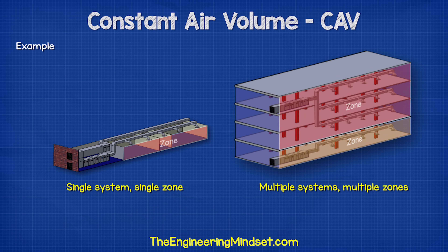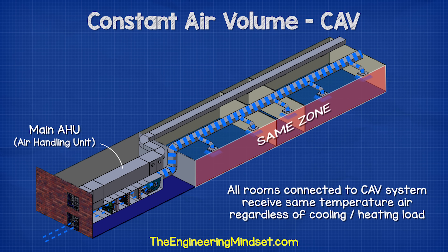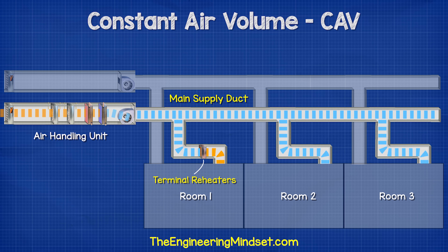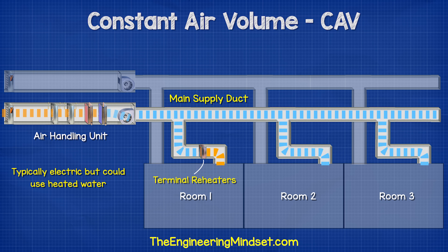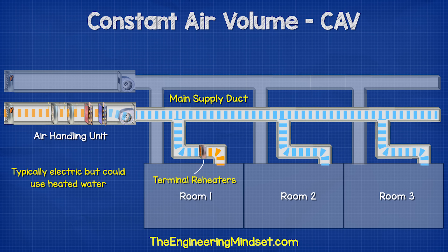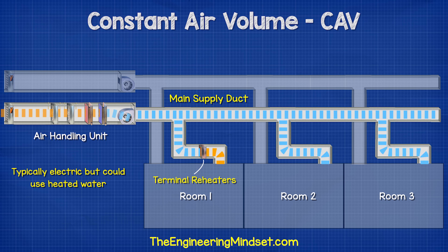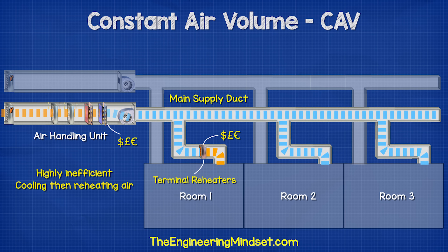Sometimes we have multiple CAV systems within a building, which gives us some zone control, with each CAV system providing a different temperature air to suit its individual zone. A possible solution to individual room control is to install terminal reheaters, usually found just before the diffuser in the ceiling. These are typically electrically powered heaters, although they could also be from a hot water system. These units will heat the local incoming air up to a higher temperature to suit the individual room. But this is very energy inefficient because you're already cooling the air down in the main AHU at significant cost, and then also paying to heat the air back up again — wasting energy and money on both cooling and heating.